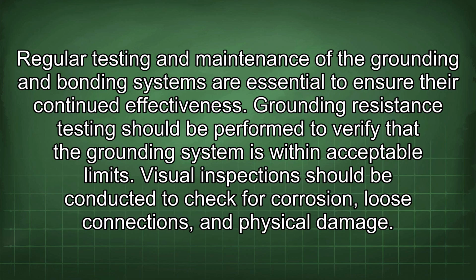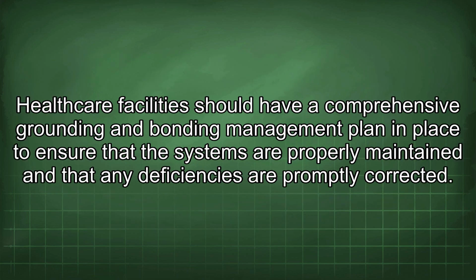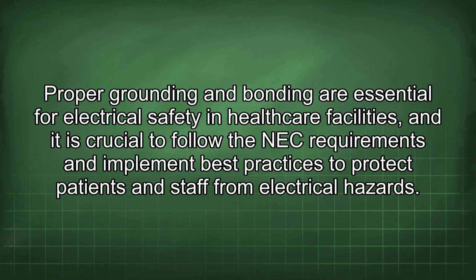Regular testing and maintenance of the grounding and bonding systems are essential to ensure their continued effectiveness. Grounding resistance testing should be performed to verify that the grounding system is within acceptable limits. Visual inspection should be conducted to check for corrosion, loose connections, and physical damage. Healthcare facilities should have a comprehensive grounding and bonding management plan in place to ensure that the systems are properly maintained and that any deficiencies are promptly corrected. Proper grounding and bonding are essential for electrical safety in healthcare facilities, and it is crucial to follow the NEC requirements and implement best practices to protect patients and staff from electrical hazards.